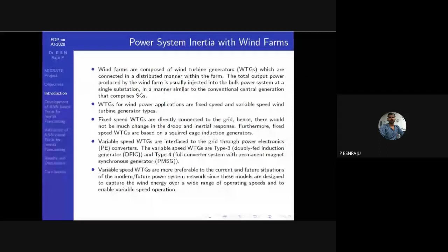So these are the various types of wind turbine generators. As we can see, we have type 1, type 2, type 3, type 4. As I mentioned, type 1 and type 2 mainly have the squirrel cage induction generator, and type 3 has the DFIG, doubly fed induction generator, with a back-to-back power converter. It is a partially rated converter. And type 4 will have a full rated converter with PMSM or other synchronous generator machines.